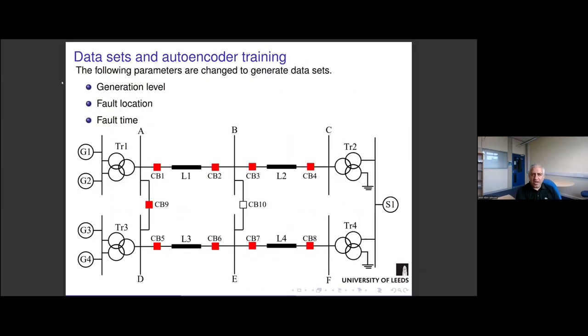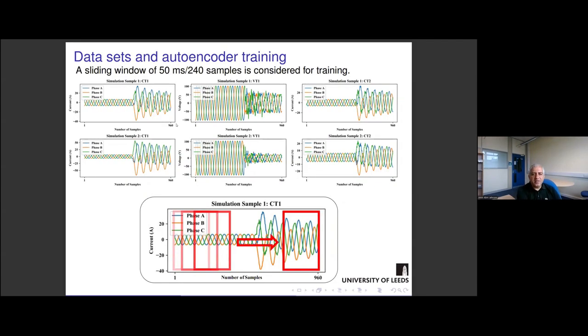In order to train the deep learning-based autoencoder, we changed the following parameters. We basically changed the generation level, the fault location, and the fault time, to generate representative data for training the autoencoder. As we can see here, we consider a sliding window of 50 milliseconds or 240 samples. The window sweeps the measurements to learn the behavior of the measurements during a fault in a transmission line or in a substation.